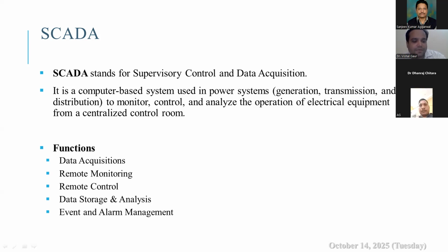The next function is data storage and analysis. SCADA stores all the major data for analysis, for taking corrective measures and decisions based on this analysis. This also helps in trend monitoring, load forecasting, and future planning. Then there is event and alarm management. Whenever abnormal conditions occur, like overload, over voltage, or frequency dip, SCADA generates alarms. This allows operators to respond quickly before things escalate and it goes up to a blackout.